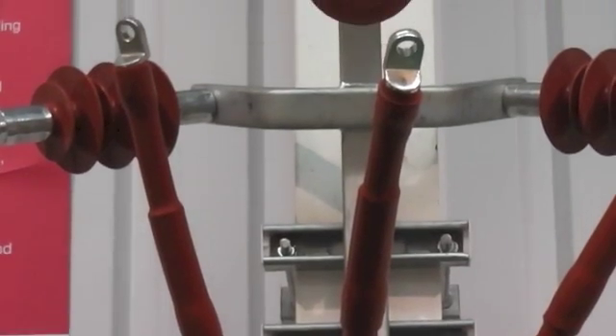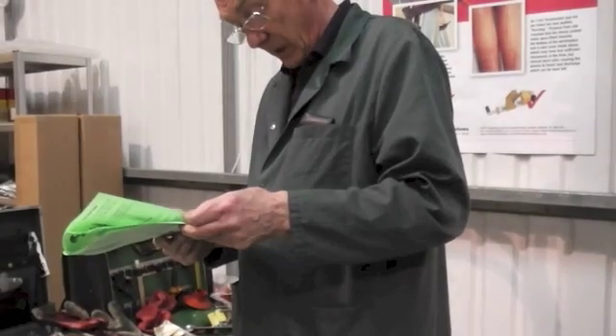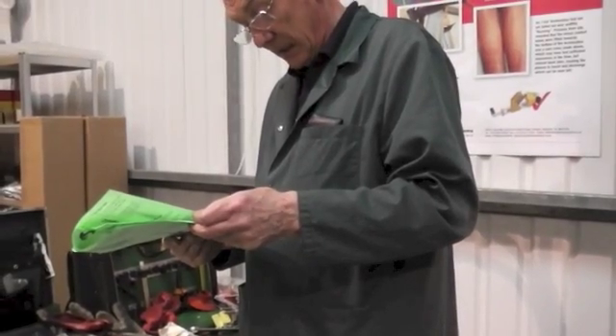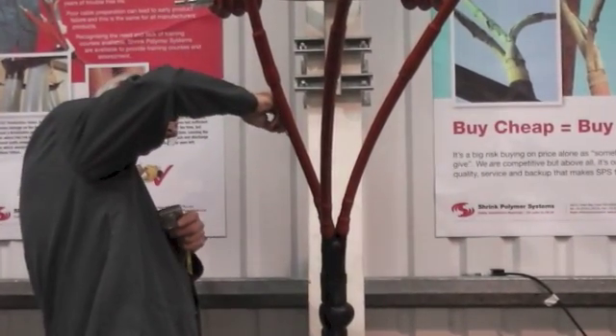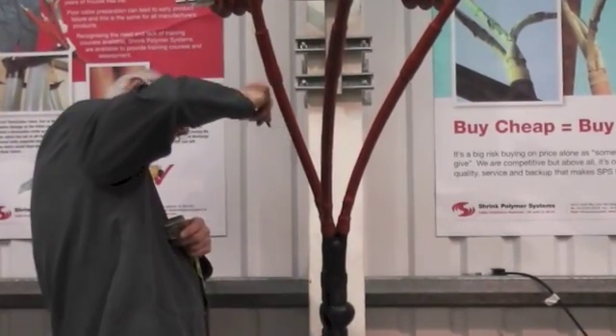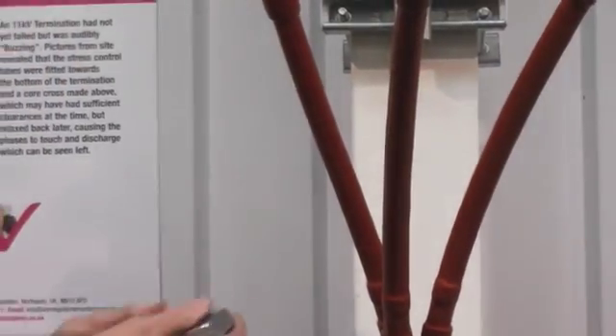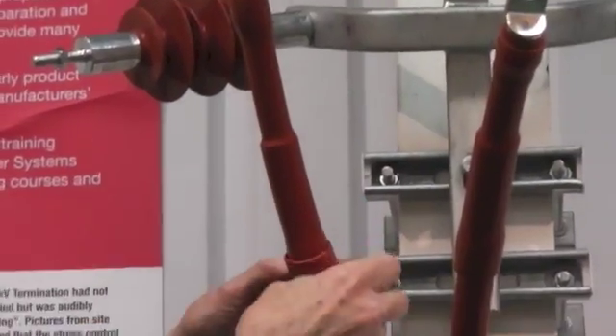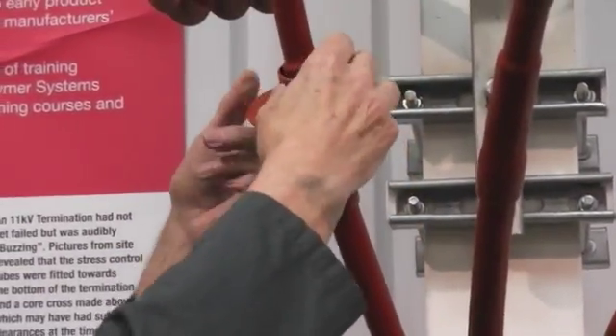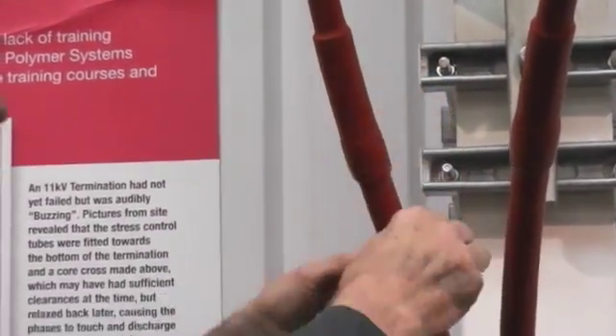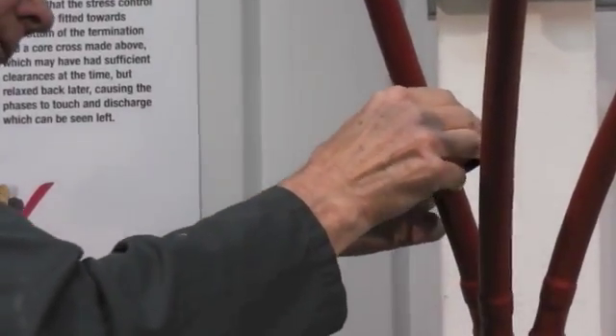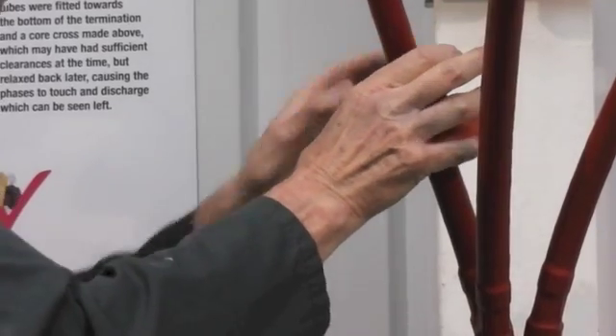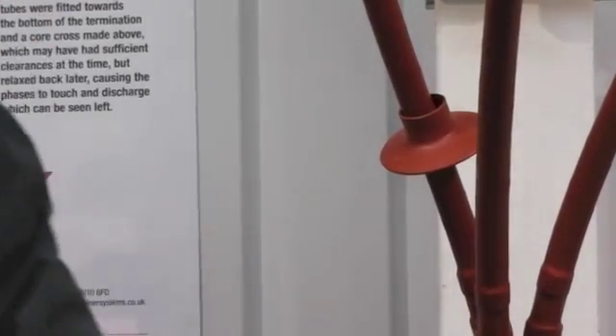And now, depending on voltage class, we're going to fit rain sheds on each of the cores. For 7.2kV, there'll be one. For 12kV, there'll be two. 17.5kV, also two. Three on 24kV, and four on 36kV.